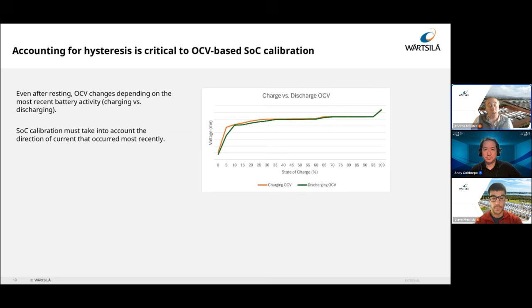The last method I'll talk about for accurately estimating SoC is accounting for hysteresis. Even after resting, OCV changes depending on the most recent battery activity — whether it was charging or discharging. You can see from the discrepancy in these voltage versus state of charge curves that even during the period where you should have the most accurate SoC estimate, the charging and discharging OCV are quite different, meaning that if you aren't accounting for this hysteresis effect, even your calibrations could be inaccurate.